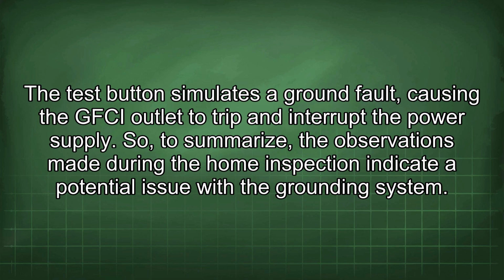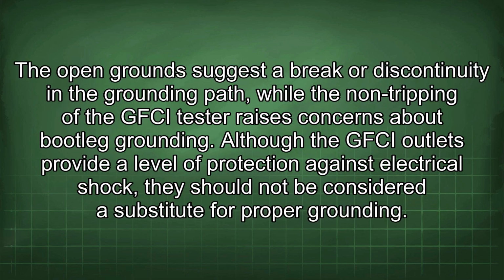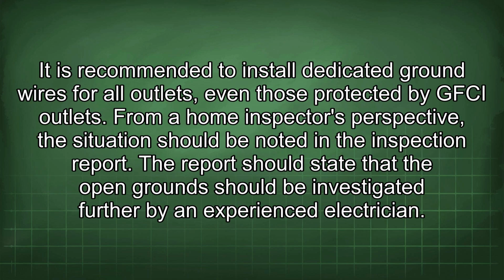So, to summarize, the observations made during the home inspection indicate a potential issue with the grounding system. The open grounds suggest a break or discontinuity in the grounding path, while the non-tripping of the GFCI tester raises concerns about bootleg grounding. Although GFCI outlets provide a level of protection against electrical shock, they should not be considered a substitute for proper grounding. It is recommended to install dedicated ground wires for all outlets, even those protected by GFCI outlets.